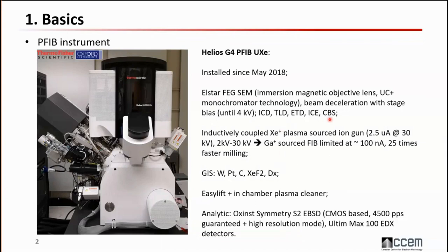The ion source on it is an inductively coupled xenon plasma, which allows us to go to currents as high as 2.5 microampere at 30 kV, compared to the gallium one, which typically is limited to 100 nanoampere. That means we have access to milling that is like 25 times faster. Concerning the GIS part, we have tungsten, platinum, and carbon for the deposition, and xenon difluoride and the DX for the etching. It's also equipped with an EasyLift and an in-chamber plasma cleaner.